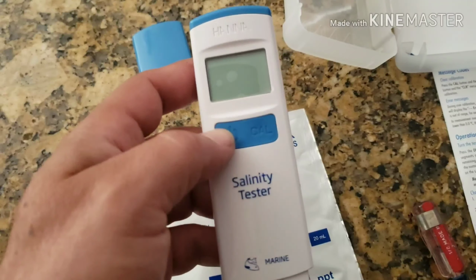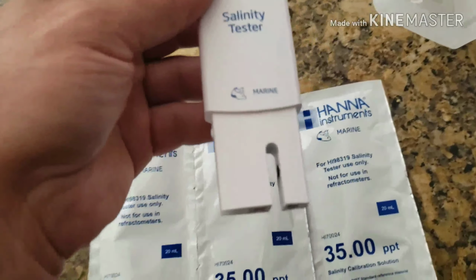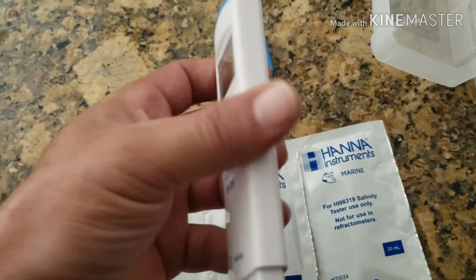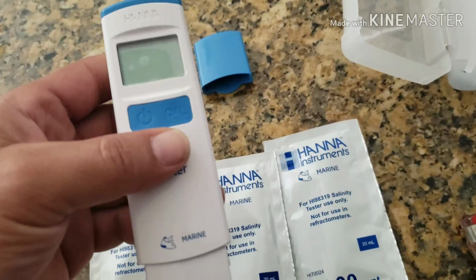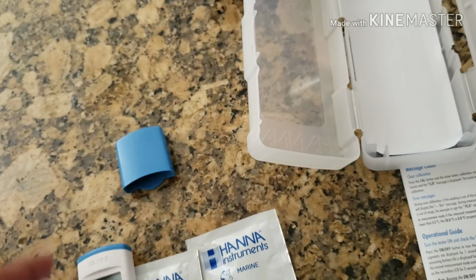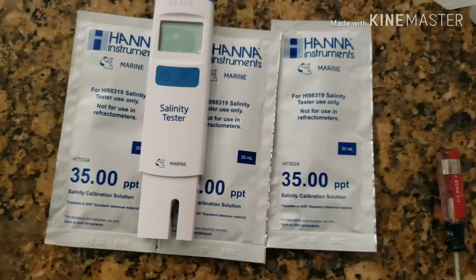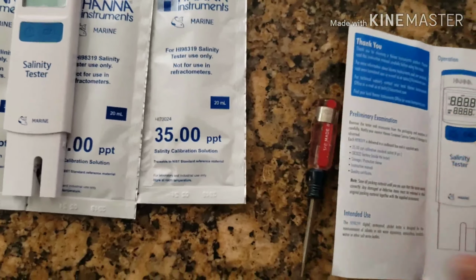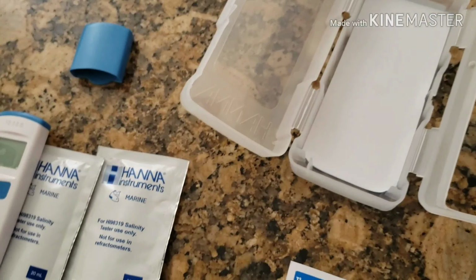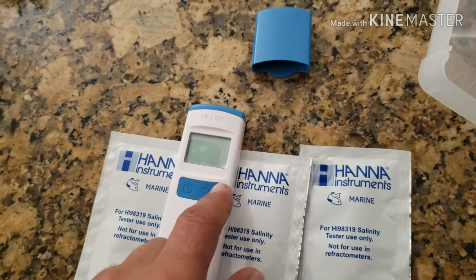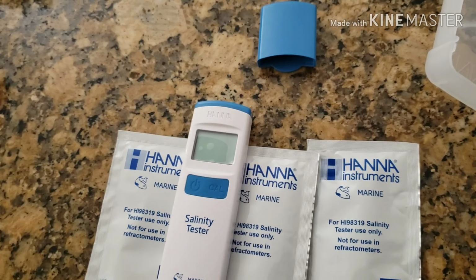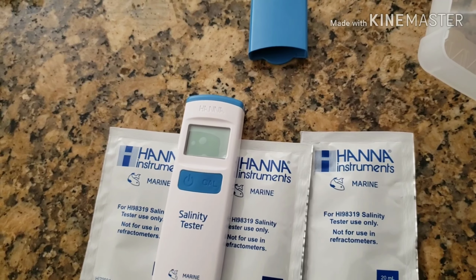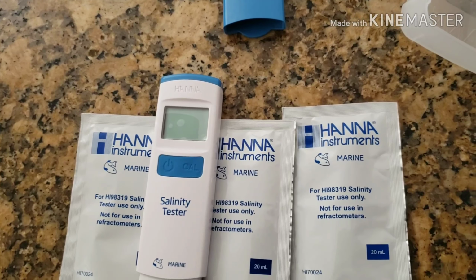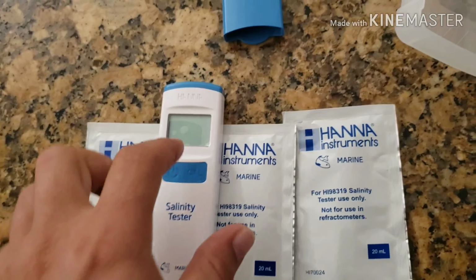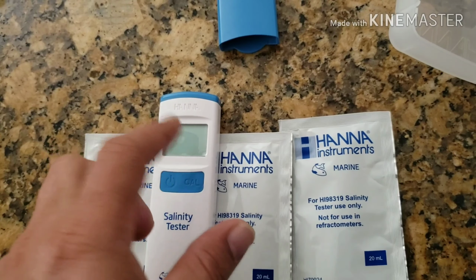So the next thing you want to do is, okay, so you've rinsed it off, you've changed the settings to your preference. Next thing you want to do is calibrate the actual tester itself. So in order to do that, you basically turn the unit on, press the calibration button. The tester will enter calibration mode, displaying 35 ppt with the cal on the screen blinking.